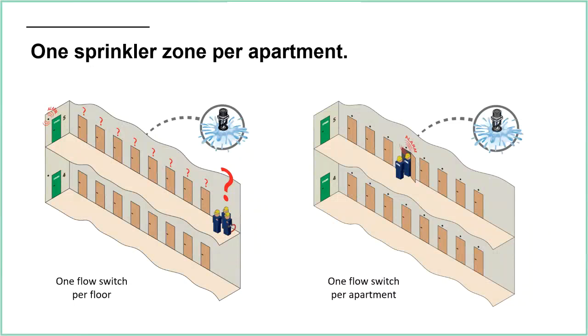Often people aren't in. Again, I am talking about London here, but I'm sure it would apply to all major cities where you've got a block of flats, and maybe one in four or one in three residents aren't going to be there, because it's maybe a second home for them. They just use it when they're working in the city. The rest of the time they're not there. So if you have a sprinkler activation, if there's a fire, then water damage, you don't really care about it, because you need to tackle the fire. But if there isn't a fire, if there has been a major leak or a malfunction or some damaged sprinkler heads, if they're activating, there'll be an alarm for the floor, but you won't know which particular apartment the activation is coming from.